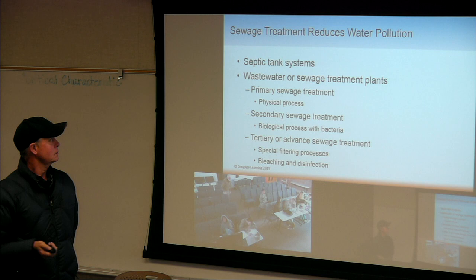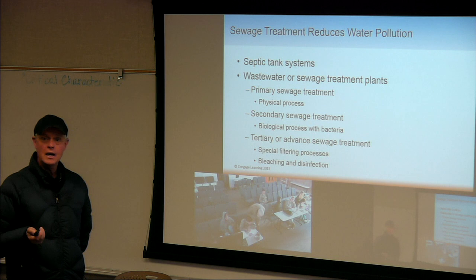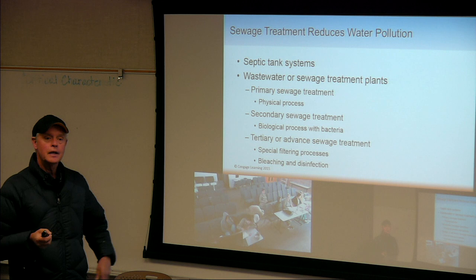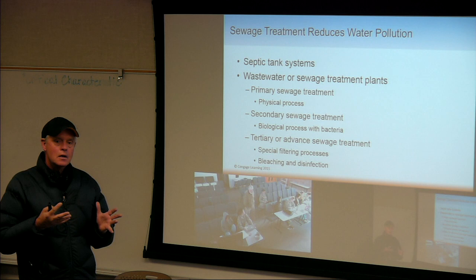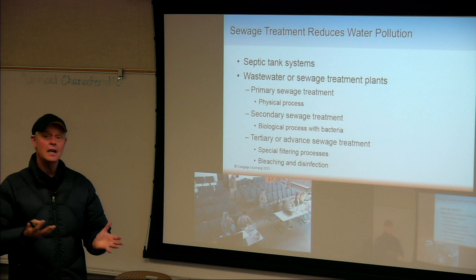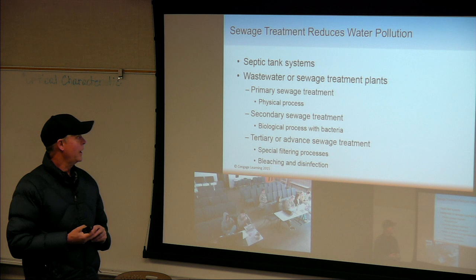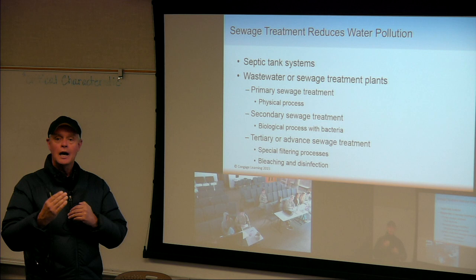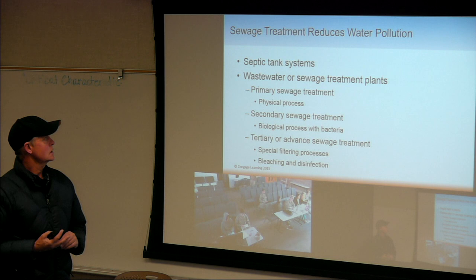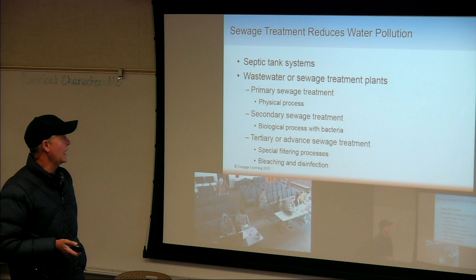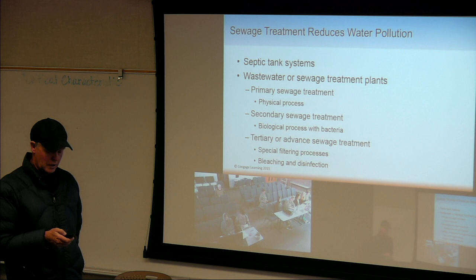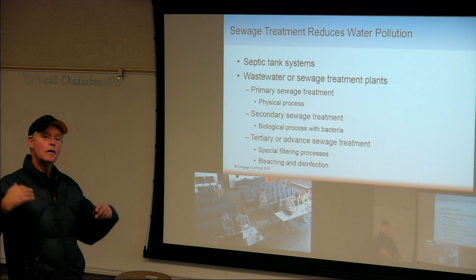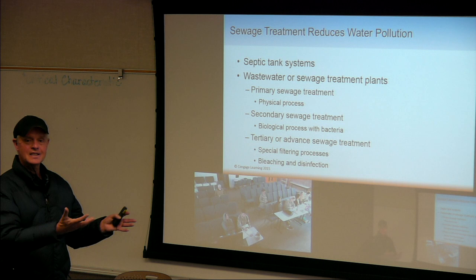Sewage treatment reduces water pollution. Septic tanks are great but inadequate — they're anaerobic and can only treat to a certain level, and septic waste from septic tanks is quite toxic. Even at Victor Valley Wastewater Treatment Plant, when a septic tank is being pumped, they have to let it into the system slowly because it can actually upset the ecology over there. Wastewater or sewage treatment plants have three phases. Primary sewage treatment is a physical process — all the stuff thrown down the toilet that doesn't belong basically gets scraped off the top.